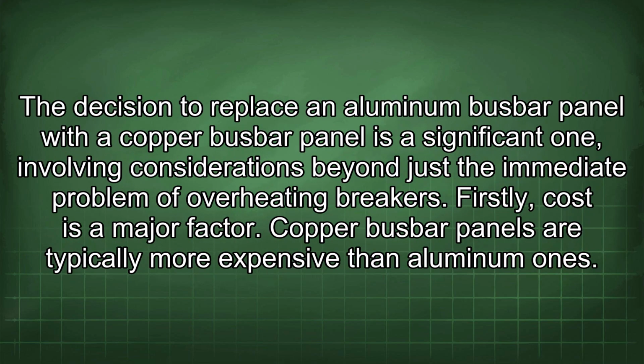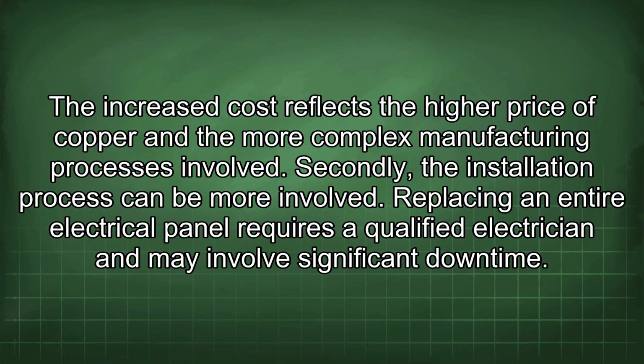The decision to replace an aluminum busbar panel with a copper busbar panel is a significant one, involving considerations beyond just the immediate problem of overheating breakers. Firstly, cost is a major factor. Copper busbar panels are typically more expensive than aluminum ones. The increased cost reflects the higher price of copper and the more complex manufacturing processes involved.